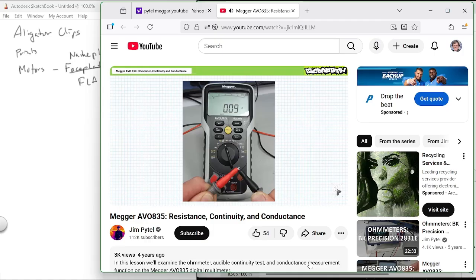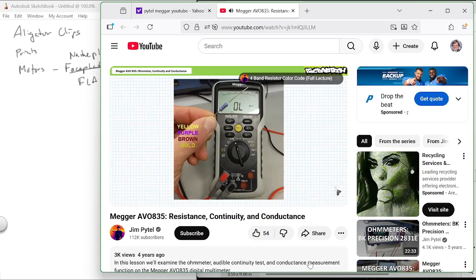Again, the element under test must be depowered and isolated from the system. Consider a resistor exhibiting the following 4-band color code: yellow, purple, brown, gold. See if you can use your understanding of the 4-band resistor color code to determine the nominal or nameplate resistance value for this resistor. By all means, pause the lecture and try this on your own. If you're tracking, you should obtain the following value. Yellow, purple, brown, gold means 4, 7, followed by 1, 0, meaning this resistor has a nominal or nameplate resistance of 470 ohms, plus or minus 5%, meaning it might actually be between 446.5 ohms and up to 493.5 ohms.